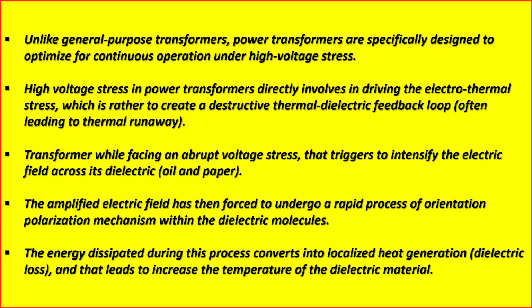A transformer, while facing an abrupt voltage stress, triggers an intensified electric field across its dielectric, that is oil and paper. The amplified electric field is then forced to undergo a rapid process of orientation and polarization within the dielectric molecules. The energy dissipated during this process converts into localized heat generation, that is dielectric loss, and that leads to an increase in the temperature of the dielectric material.